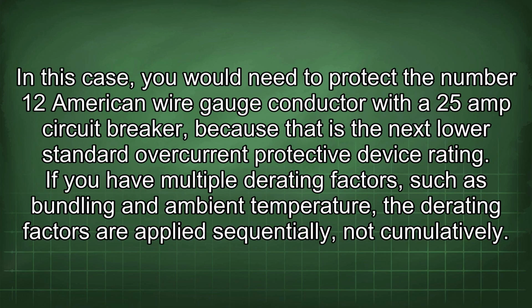In this case, you would need to protect the number 12 American wire gauge conductor with a 25 amp circuit breaker because that is the next lower standard overcurrent protective device rating. If you have multiple derating factors, such as bundling and ambient temperature, the derating factors are applied sequentially, not cumulatively.